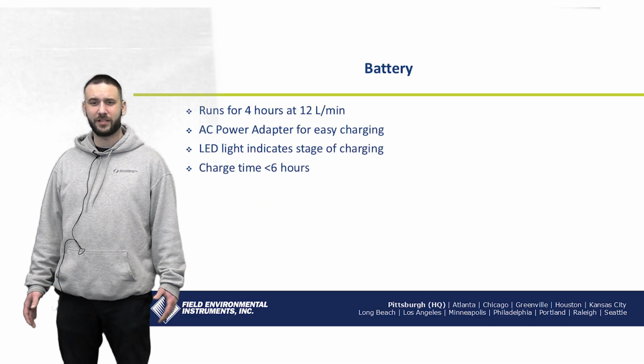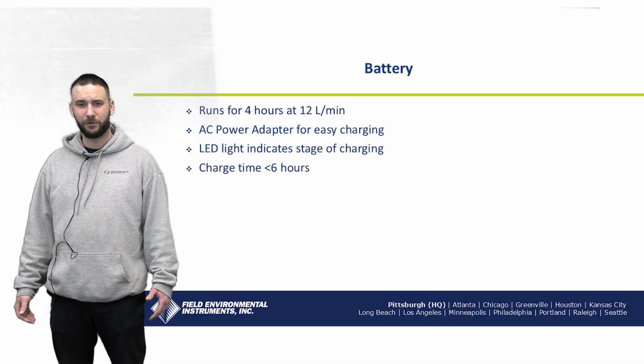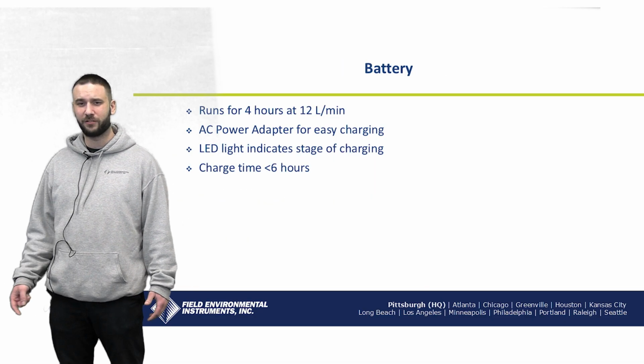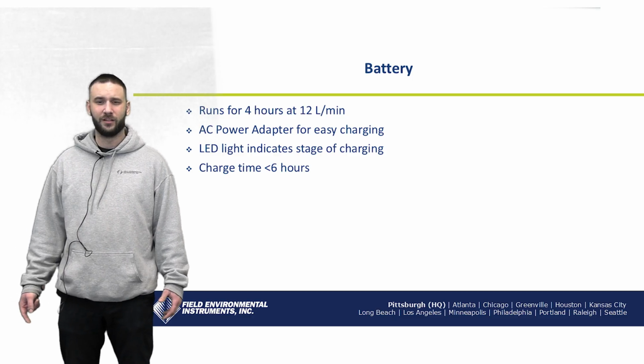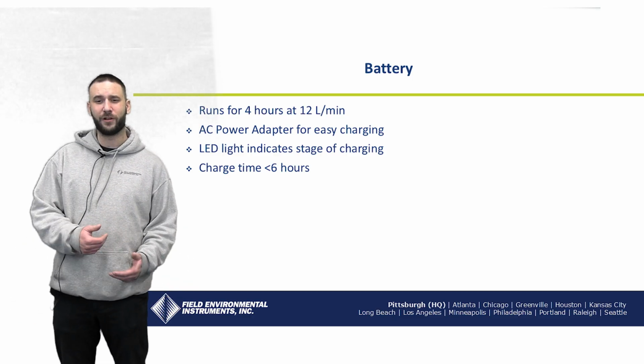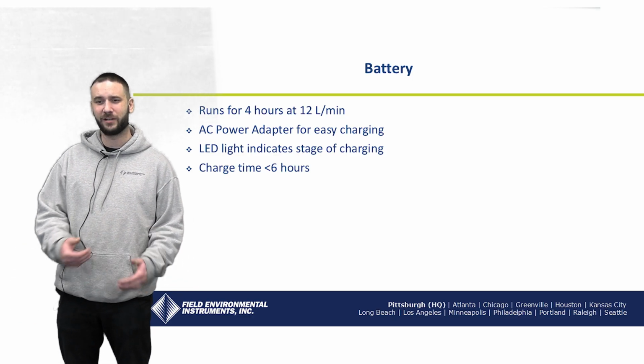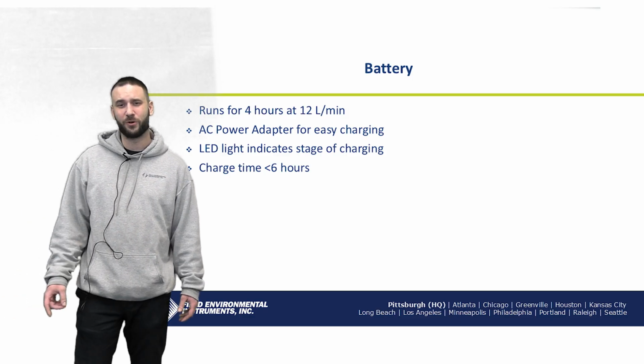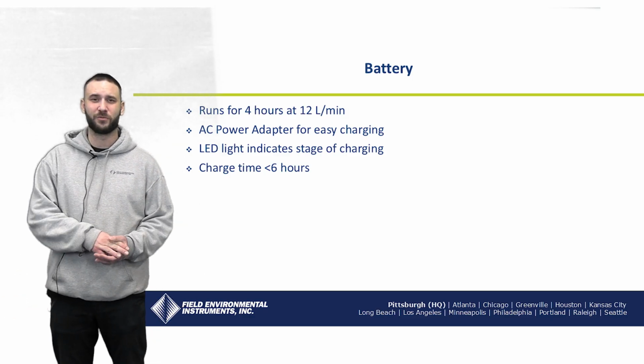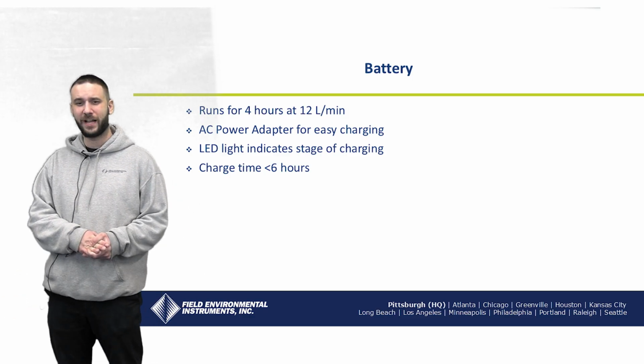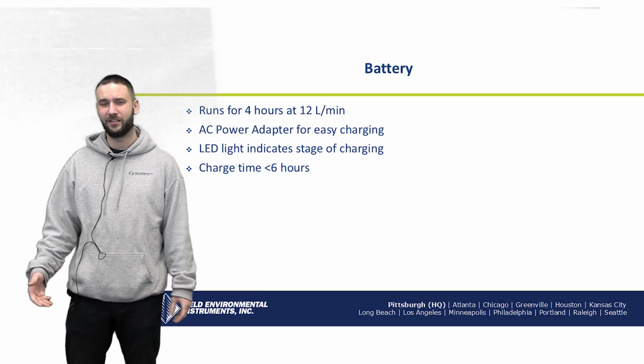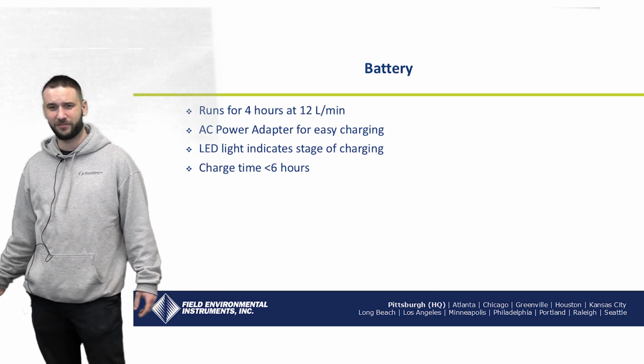A big strength of the Vortex 3 is its battery life. It runs for 4 hours at that 12 liter a minute flow maximum. Now, whenever you have the flow going at that high, it creates more back pressure. Whenever more back pressure is created, it puts more strain on the battery. So the fact that you can get 4 hours at that high of a flow rate is very impressive.